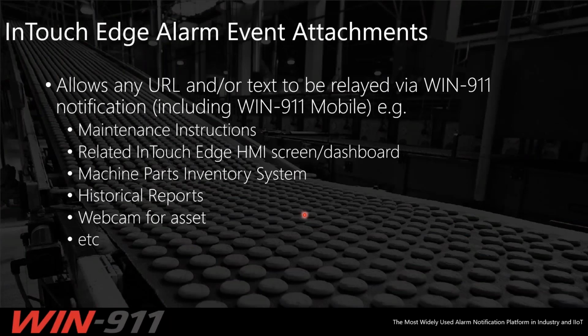And so one of the features they've added is that you can put a URL with a tag under a custom field, and in my scenario, I just put a link to our KB solutions. And so when the alarm is triggered and the operator receives the alarm on their mobile device with the WIN-911 mobile app, once they tap into the alarm and see the details, there will be an option for attachments. And from there, they would see their URL to take them to where they need to go.